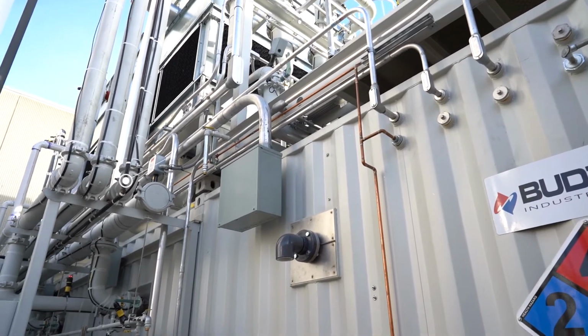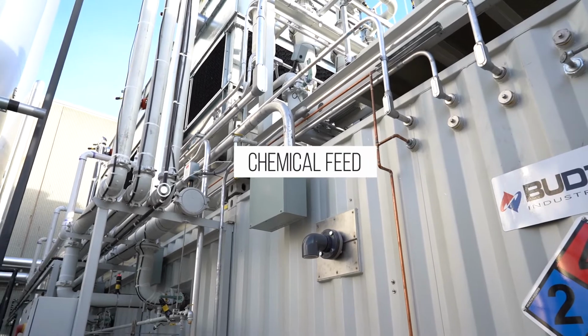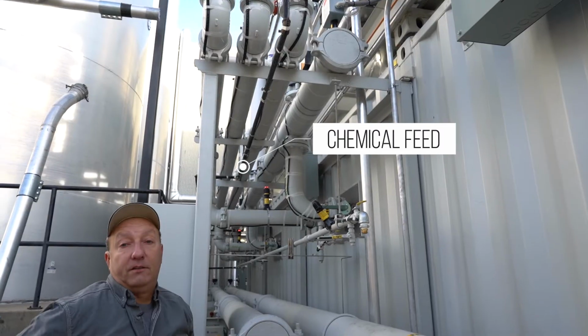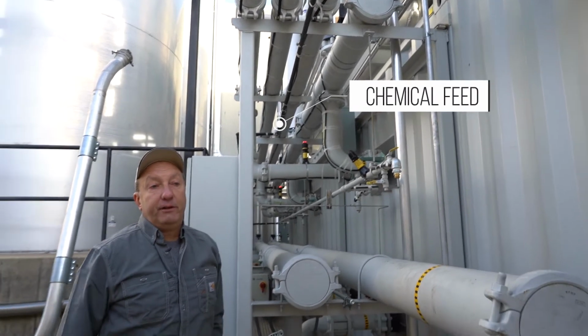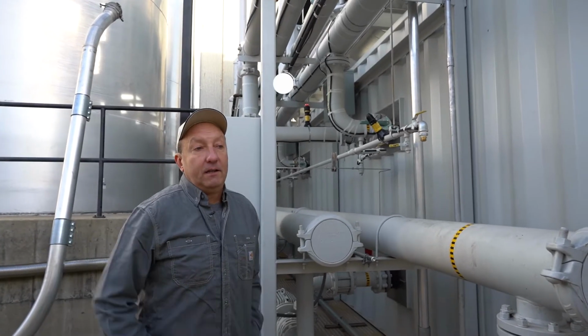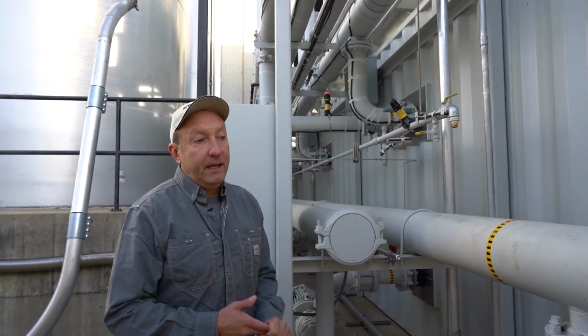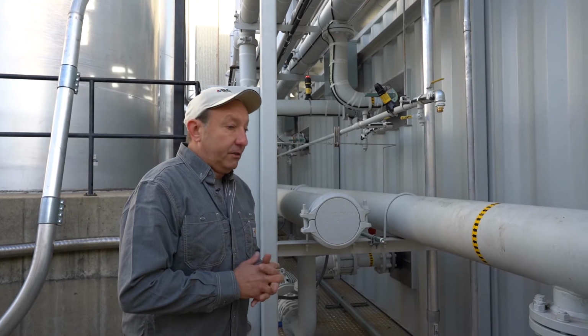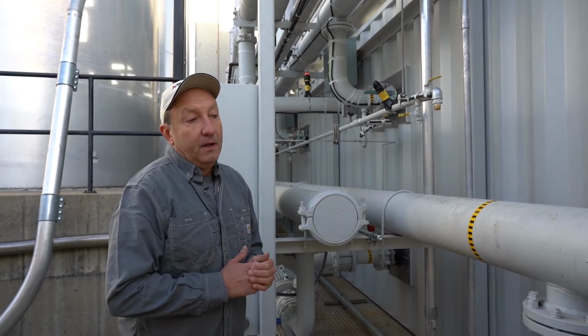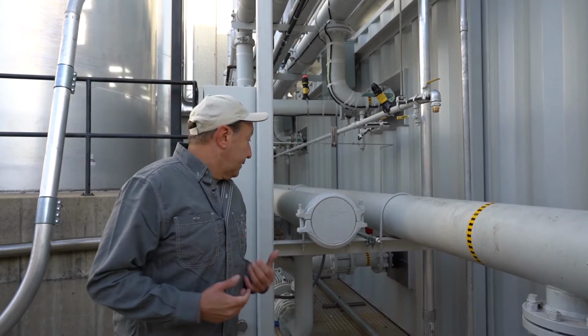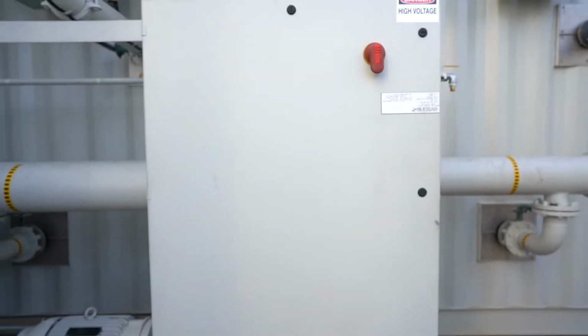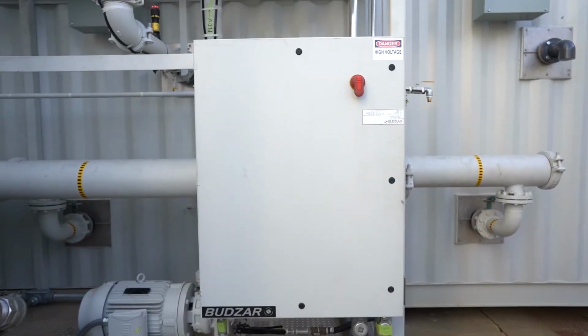These smaller lines here, 3/4 inch black pipe, that's for the chemical feed. The customer here is responsible for treating the tower water and keeping that in good condition. They monitor pH and just keep the water in good condition so we don't foul the towers and keep everything efficient. This enclosure is dedicated for the process pumps.